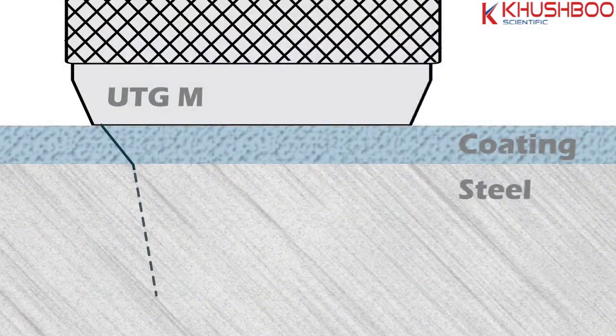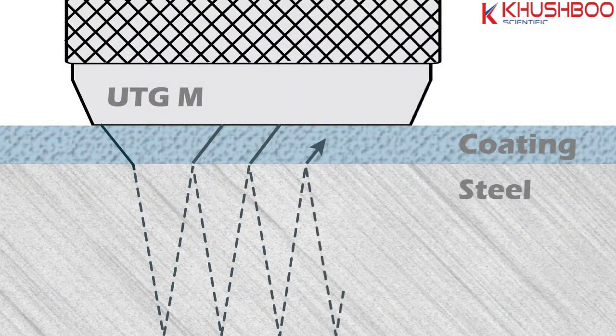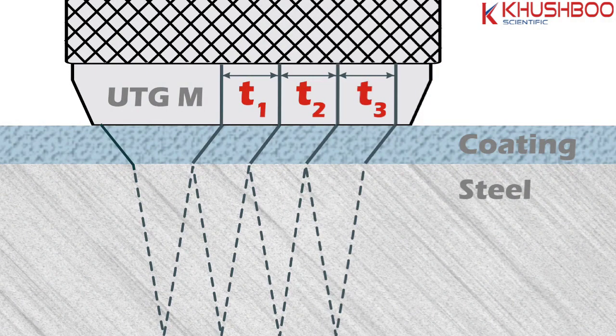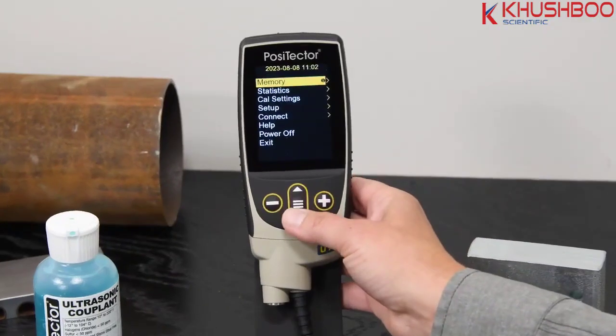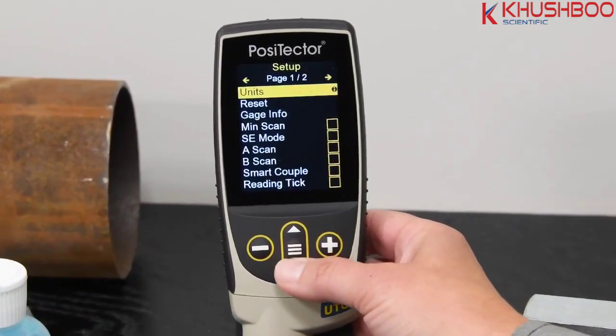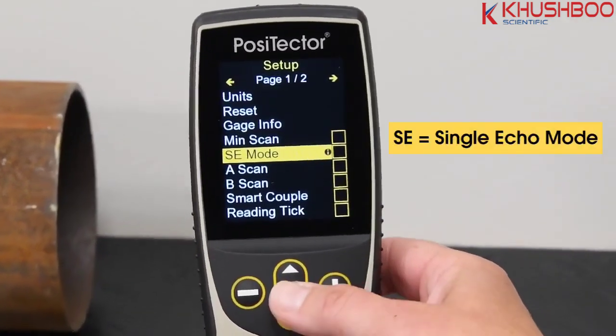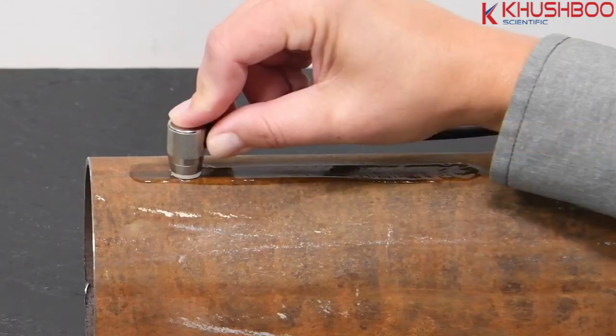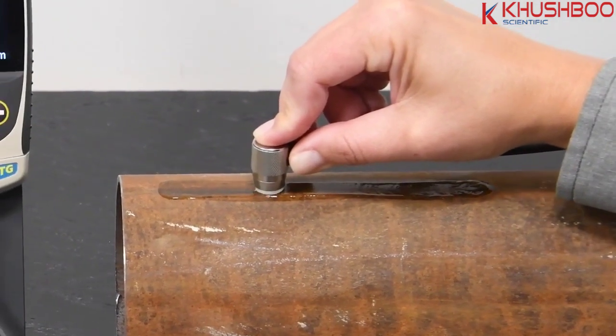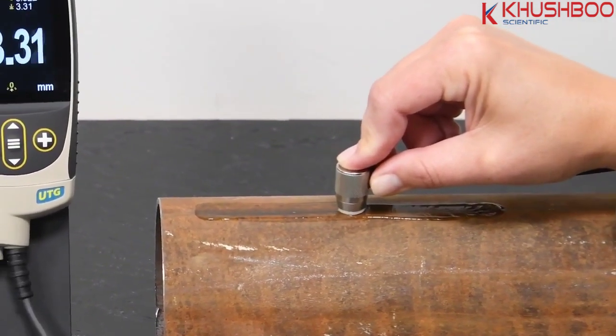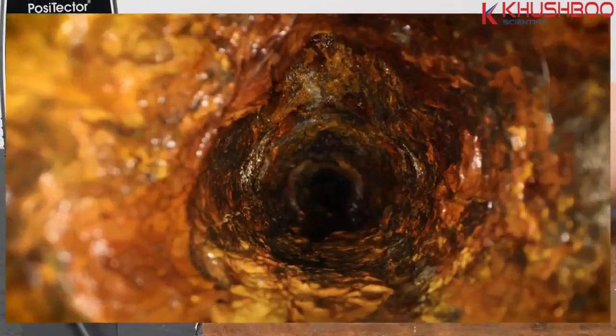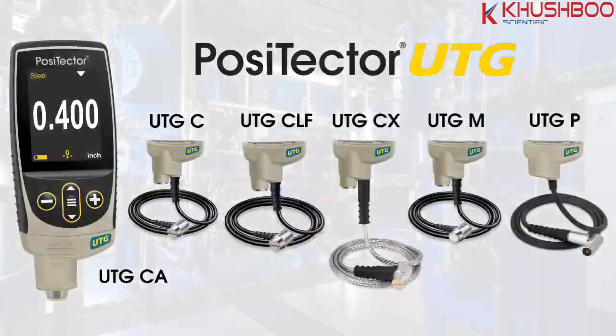The PosiTector UTG M measures 3 or more echoes to eliminate the effect of the coating. Multiple echo mode can also be disabled to detect pits or flaws and increase the measurement range. The multiple echo method requires a parallel back wall, and extremely corroded applications may be challenging to measure.